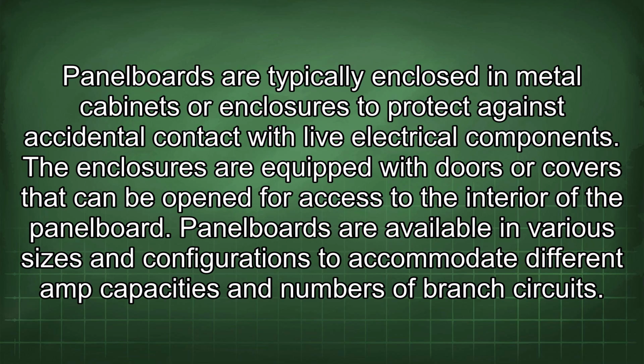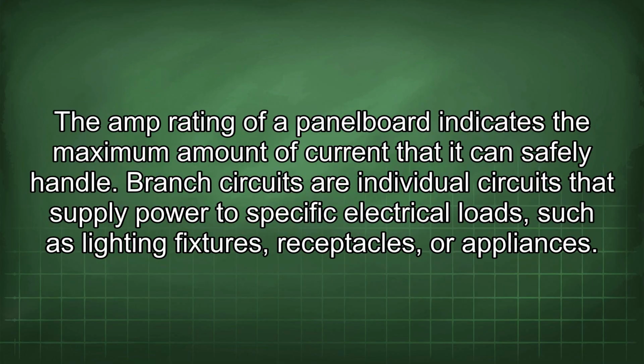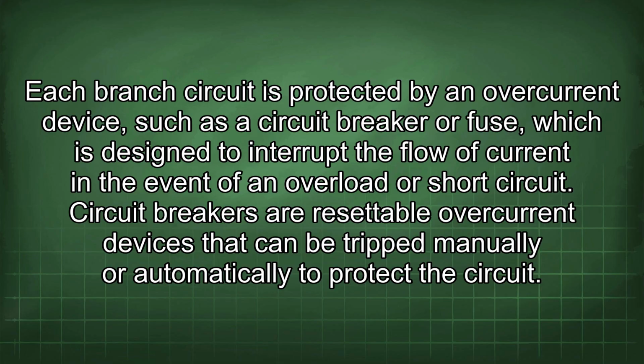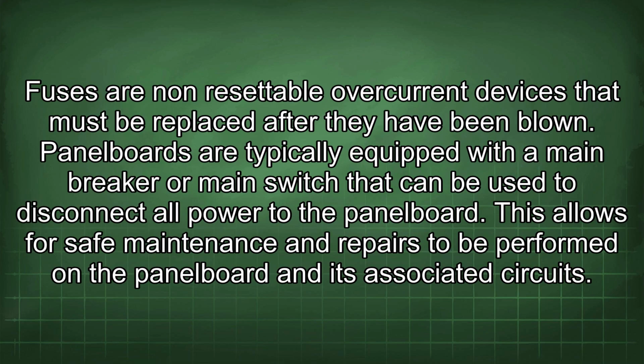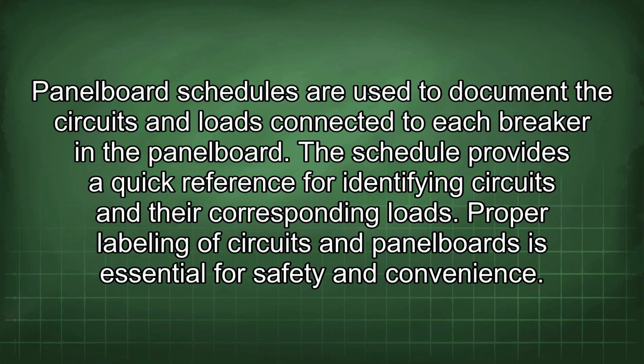Panel boards are available in various sizes and configurations to accommodate different amp capacities and numbers of branch circuits. The amp rating of a panel board indicates the maximum amount of current that it can safely handle. Branch circuits are individual circuits that supply power to specific electrical loads, such as lighting fixtures, receptacles, or appliances. Each branch circuit is protected by an overcurrent device, such as a circuit breaker or fuse, which is designed to interrupt the flow of current in the event of an overload or short circuit. Circuit breakers are resettable overcurrent devices that can be tripped manually or automatically to protect the circuit. Fuses are non-resettable overcurrent devices that must be replaced after they have been blown. Panel boards are typically equipped with a main breaker or main switch that can be used to disconnect all power to the panel board. This allows for safe maintenance and repairs to be performed on the panel board and its associated circuits. Panel board schedules are used to document the circuits and loads connected to each breaker in the panel board.